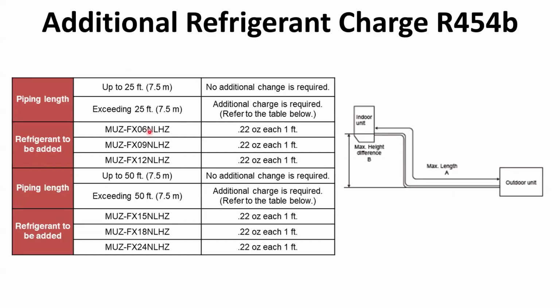Now, what's changed? You notice these models, the FX06 through 12, we used to do so many ounces per 5 feet, it was 1.08 ounces. Now they're listing it as 0.22 ounce per foot. But if you do the math, it's basically the same amount: 0.22 times 5 feet is 1.10 ounces per 5 feet. So it's basically the same, but now they're listing it per foot. Just make note of that.